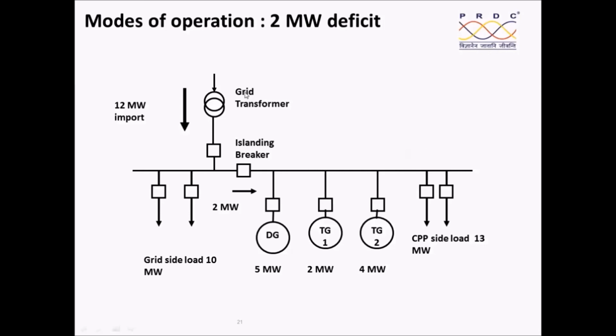Therefore, one is the captive power plants, 5 megawatt, 2 megawatt, 4 megawatt, a CPP with a load of about 13 megawatt. Grid side load is about 10 megawatt. In this case, from the grid, we are importing 12 megawatt, load is 10 megawatt. Therefore, through the islanding breaker, there is a flow of about 2 megawatt into the system. During this condition, if islanding occurs, depending upon what cushion is available on my generators, whether they can give additional power. If there is a slight cushion available, then I need not do the load shedding. If there is no cushion available, then we need to do the load shedding.